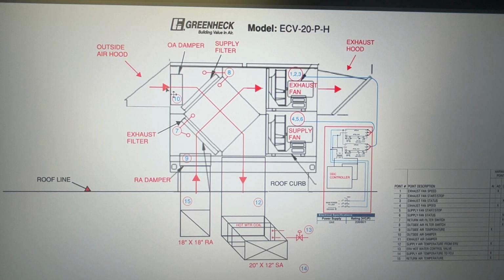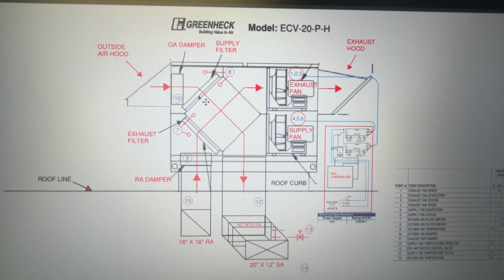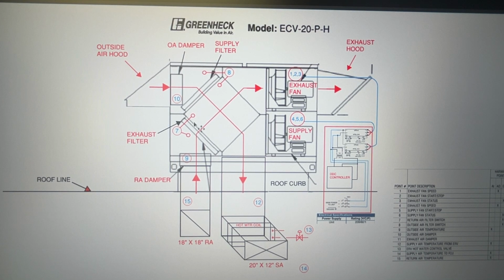But this airstream comes out through here and comes across the core. So here's our core. We have exhaust filters here. This is our return air damper. So that fresh air comes across the core and goes and serves the space. When it's used in the space, it comes back up this return across the core. We have an exhaust fan chamber here, which exhausts that used air to the outside. We also have a supply air fan here that's pulling that outside air in to serve the space.